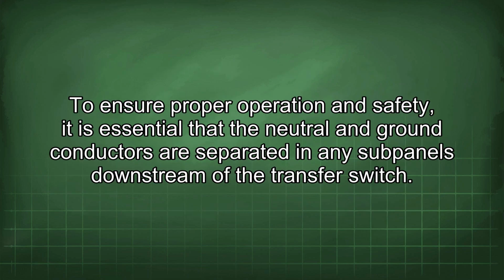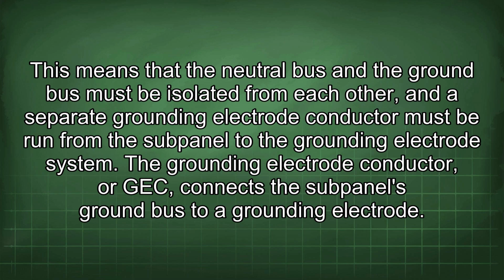To ensure proper operation and safety, it is essential that the neutral and ground conductors are separated in any subpanels downstream of the transfer switch. This means that the neutral bus and the ground bus must be isolated from each other, and a separate grounding electrode conductor must be run from the subpanel to the grounding electrode system.